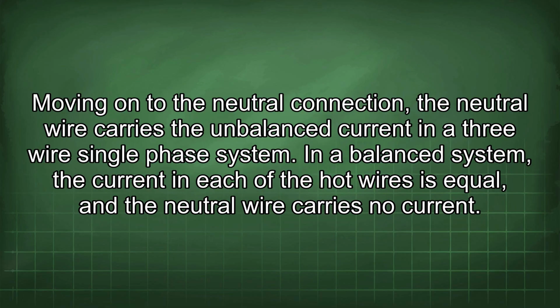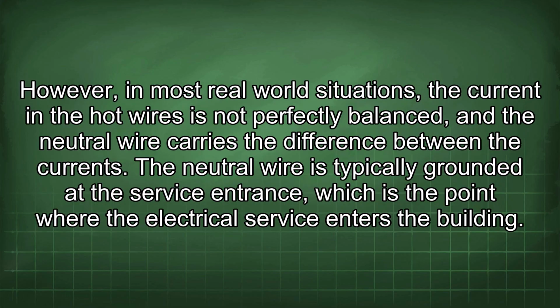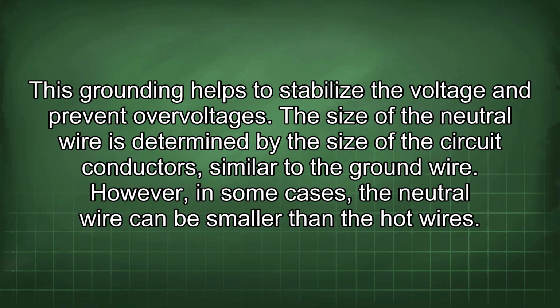Moving on to the neutral connection, the neutral wire carries the unbalanced current in a 3-wire single-phase system. In a balanced system, the current in each of the hot wires is equal and the neutral wire carries no current. However, in most real-world situations, the current in the hot wires is not perfectly balanced, and the neutral wire carries the difference between the currents. The neutral wire is typically grounded at the service entrance, which is the point where the electrical service enters the building. This grounding helps to stabilize the voltage and prevent overvoltages.